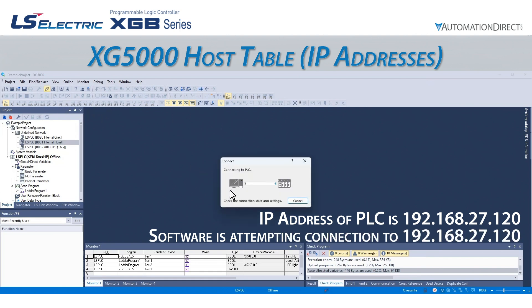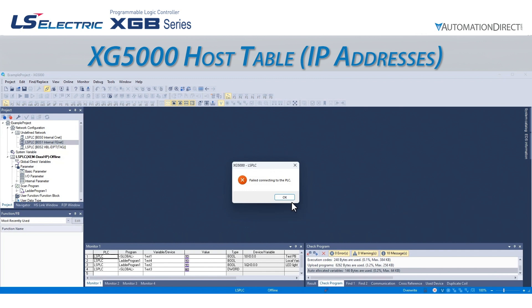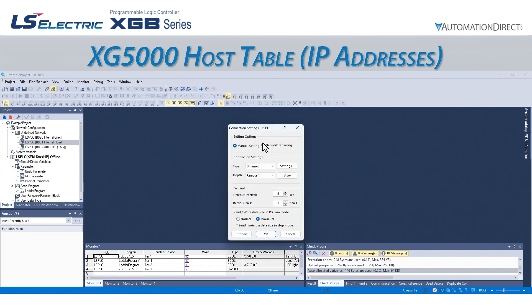In our example, we added the IP address of our drive, but we didn't add the IP address of our computer running XG5000. If we attempt to connect to the PLC using the Ethernet connection, we get a failed connecting to the PLC error, indicating the PLC refused the connection. In this case, the USB port on the CPU will still allow us to connect.